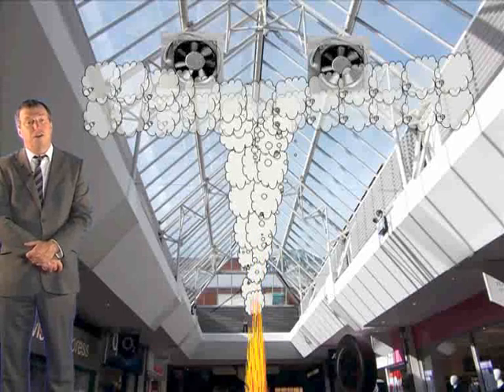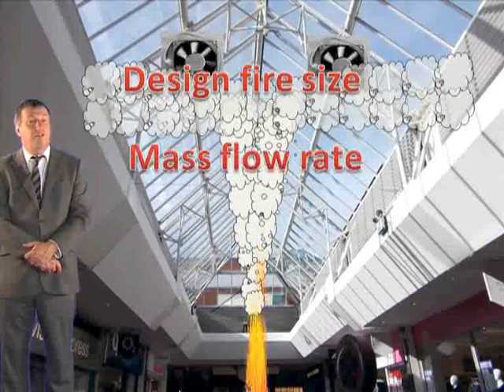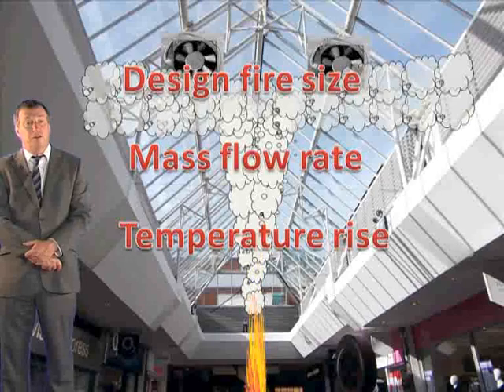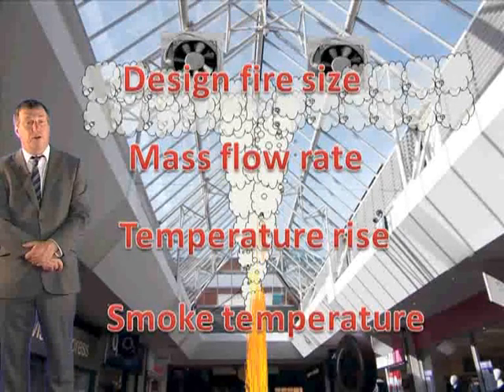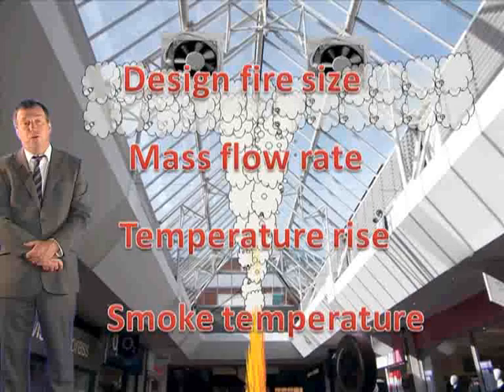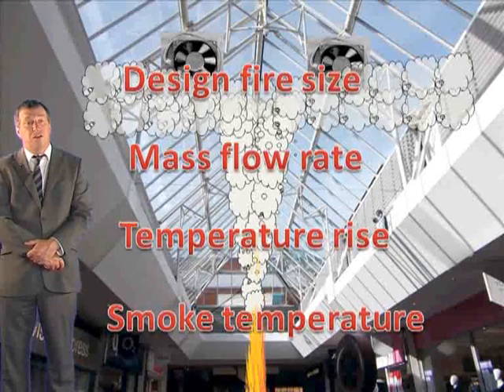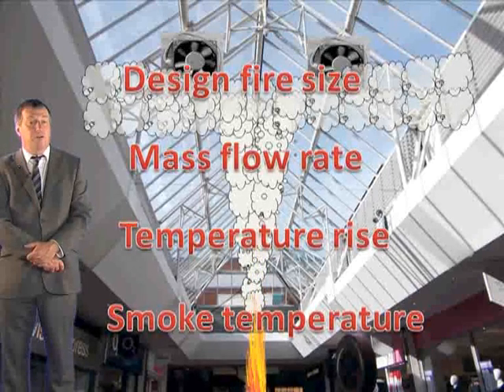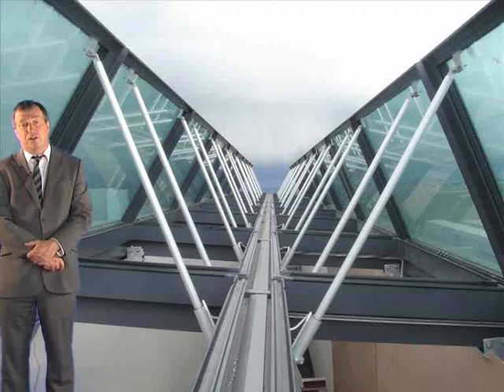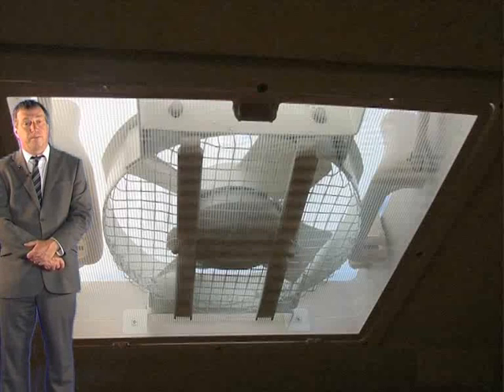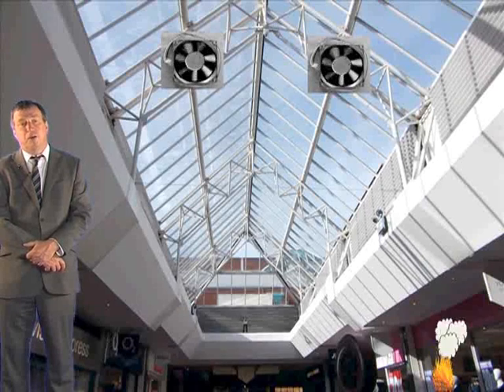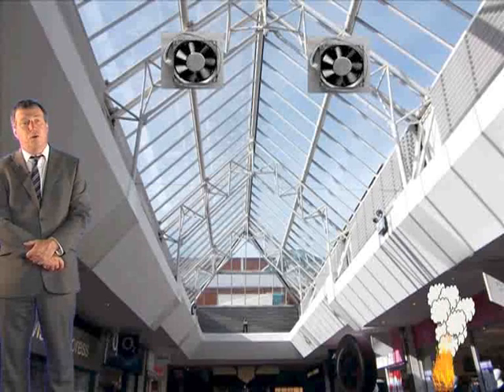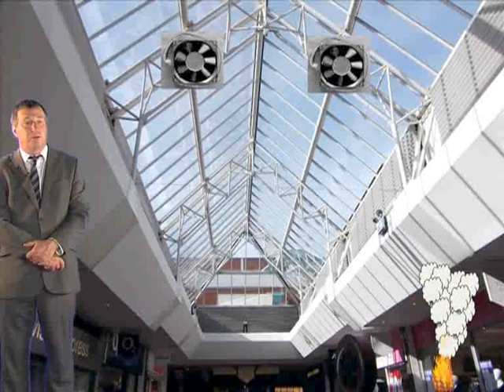You now have information on the design fire size, the mass flow rate of smoke, the average temperature rise within the smoke layer, and the actual temperature of the smoke layer. With this and some few other pieces of essential information, you can now calculate the requirements for smoke exhaust, whether that be by natural ventilation or by powered fans. Before we calculate the smoke exhaust requirements, we should say a few words about acceptable smoke temperatures.